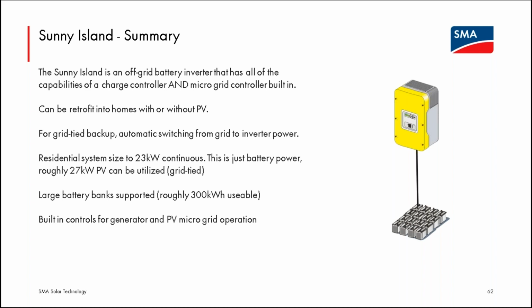And again, their inverter has to work this way if the utility grid is doing that frequency change or a Sunny Island. So there should not be a warranty implication. But again, I think for installers to best protect the interest of their customers, they should verify with the manufacturer if it's not an SMA PV inverter. So technically it will work correctly, but to provide maximum coverage, I guess, for the homeowner or the existing PV system owner, make sure there's no warranty implication for implementing it in an AC microgrid.